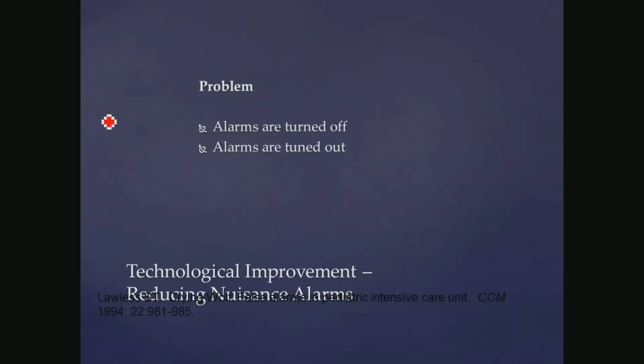Some other problems with nuisance alarms, and this is one of the things, I was just talking to somebody about the JCAHO inspection. They were saying that alarm management of nuisance alarms is one of the things they're trying to hone in on to find out how the hospital is responding. Not only do we have situations where the alarms are turned off, there's been cases of a baby found, well, no, it was a child actually, a small child, I think it was a 3-year-old. The pulse oximeter sensor was on, the pulse oximeter was turned on, the pulse oximeter was alarming, but the alarms were turned off, they were silenced. So never picked up on the fact.